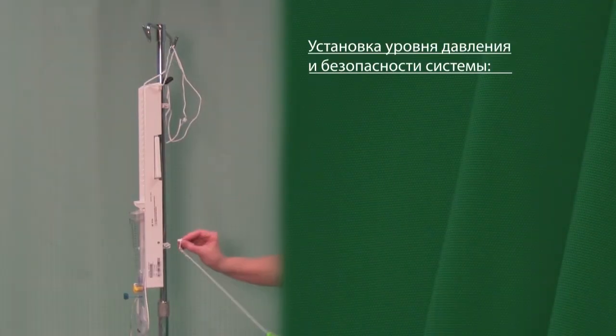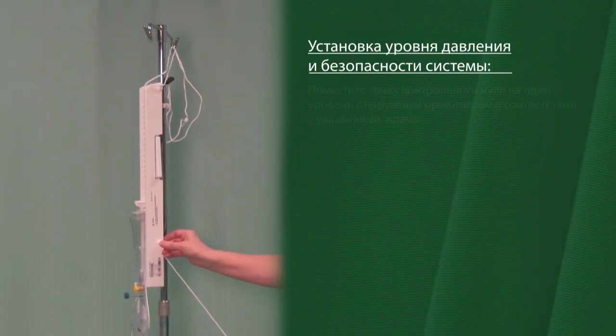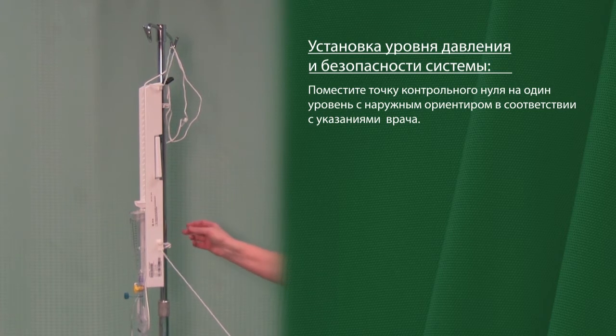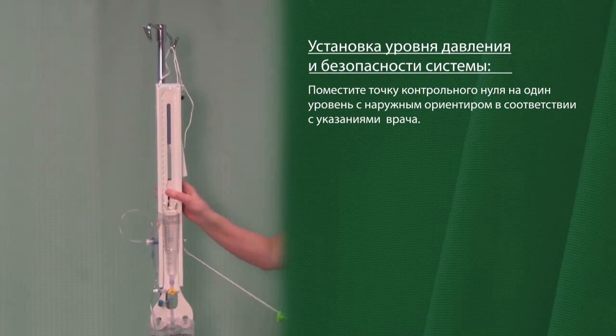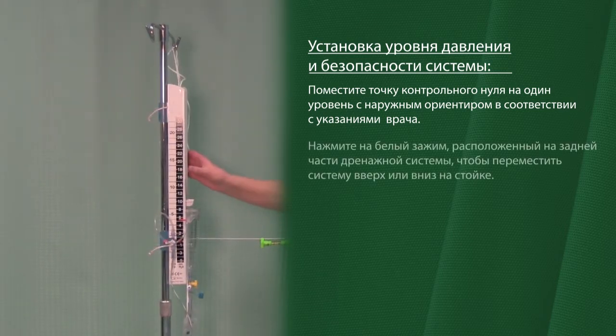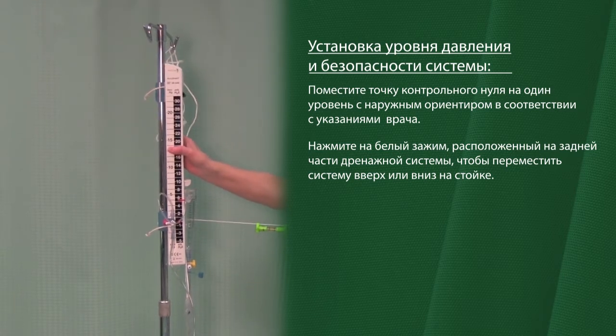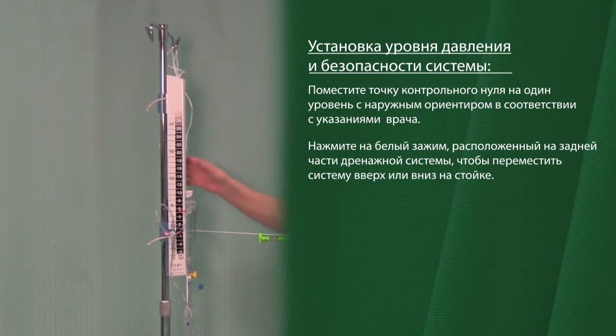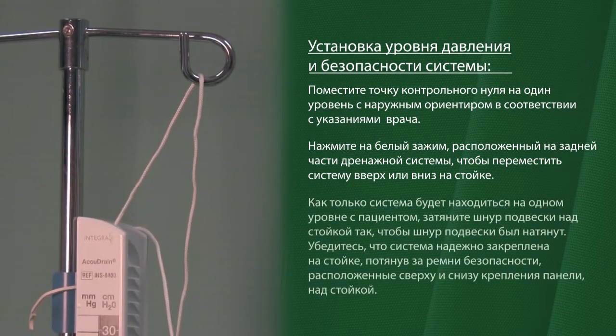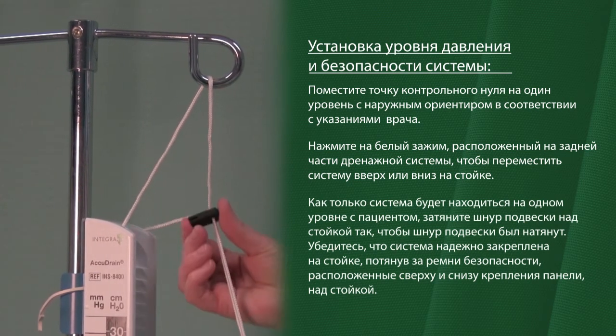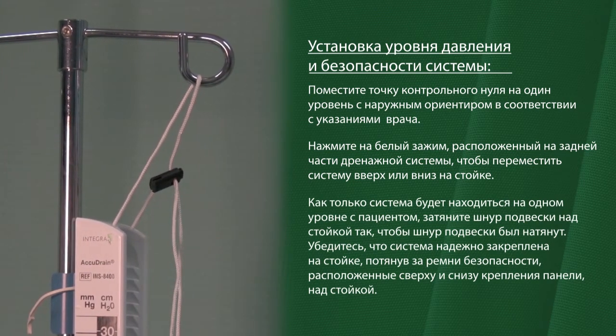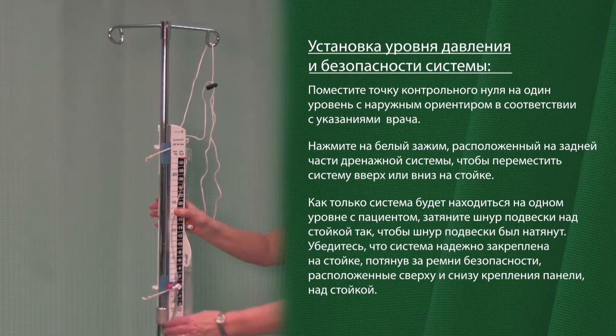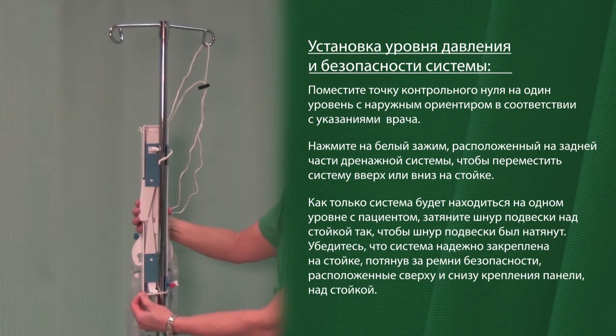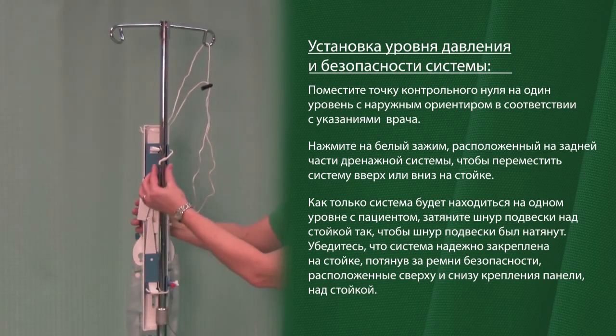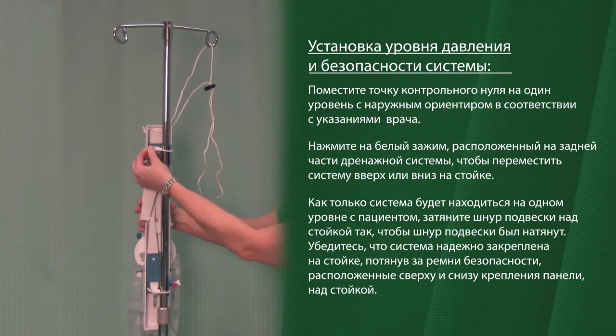Setting the pressure level and securing the system. Place the zero reference at the external landmark of the patient as ordered by the physician. Press the white clamp behind the drainage system to move the system up or down the pole. Once the system is level with the patient, tighten the suspension cord over the IV pole so that the suspension cord is taut. Ensure the ACCUDRAIN system is securely attached to the pole by pulling the security straps located on the top and bottom of the panel mount over the IV pole.